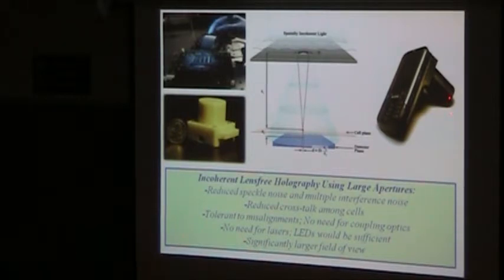So this light source here that's installed at the back of this tube is a simple light-emitting diode. The same is true here, and you can also have a light-emitting diode there. So by using a light-emitting diode that's coupled to a very large aperture, which in this case is on the order of 50 to 100 micrometers, we create partial coherence of light, so that by the time the light waves travel a distance of a couple of centimeters between the LED and the sample, they acquire partial spatial coherence, so that if you ask one of these cells, it's being illuminated by a perfect plane wave with a constant phase, and the next cell would experience something else. But for each individual cell hologram, we have spatial and temporal coherence sufficient to record these holograms.